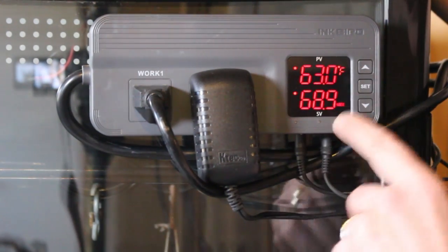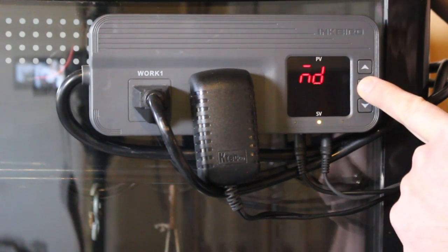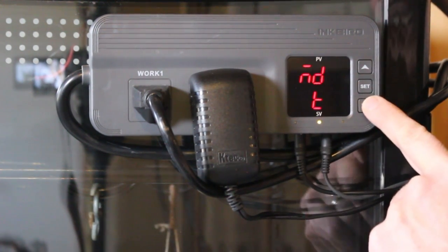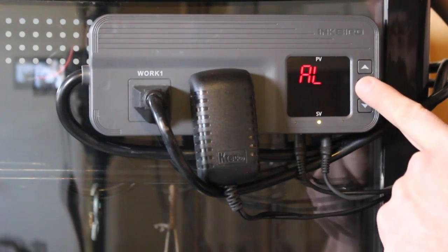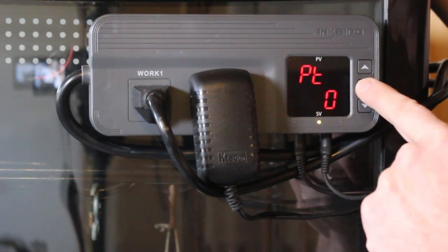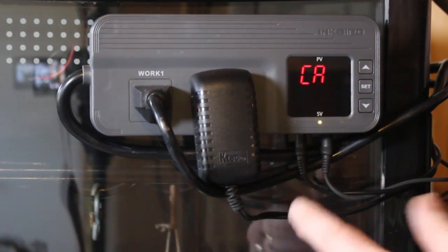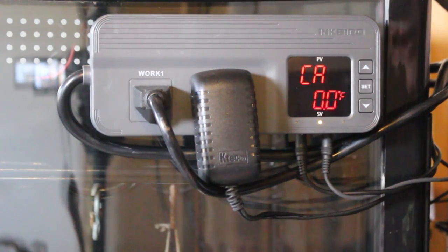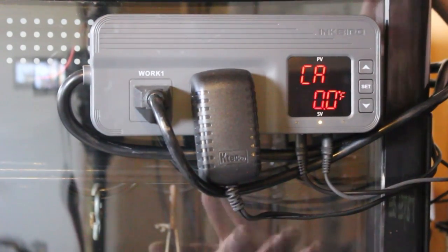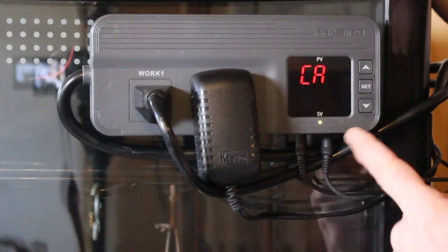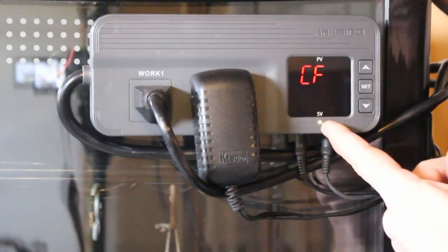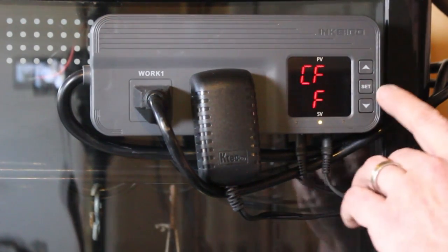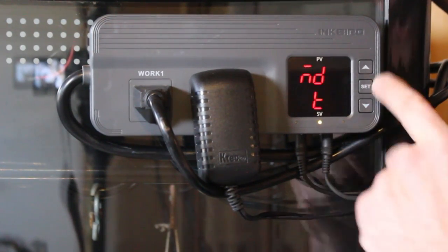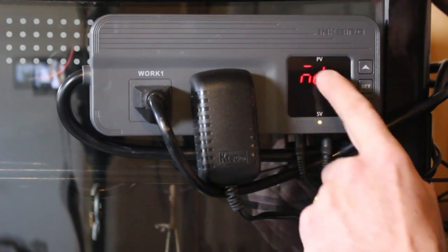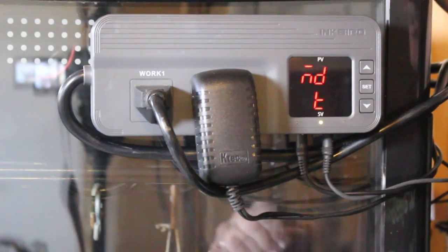If you stand around and talk while you're programming it, it'll just kick out of the program mode. And in fact, save all the settings you've already made. So we can just go down through and get back to where we were. Alarm low, compressor time, calibration, 0.0 degrees Fahrenheit. You can actually set this if you find that you've got this plugged in and it's off, the temperature probe isn't working quite right. You can actually change this and put a little bit of a calibration adjustment in there. I found this thermometer is dead on, so I just leave that alone. And then the last setting is Celsius or Fahrenheit. I live in North America and we tend to use Fahrenheit a little bit more often. And we're back to this. I have no idea what N bar D means, but it's basically the top of the menu.